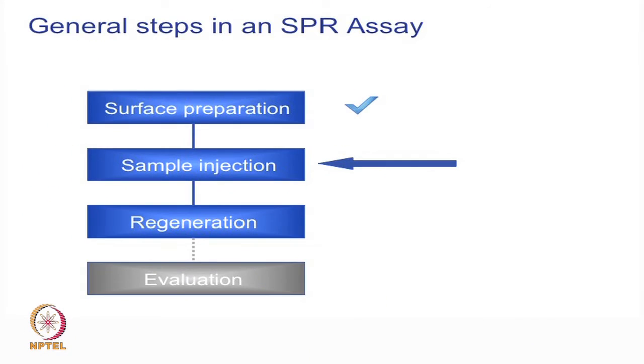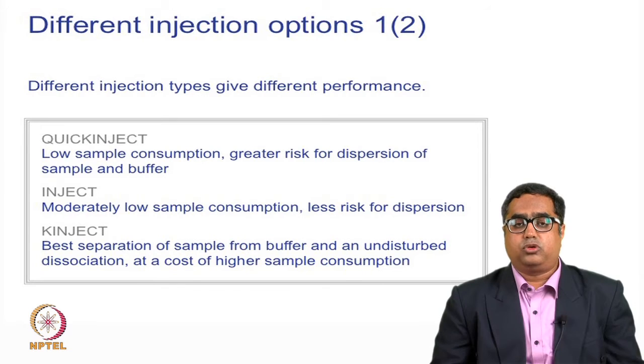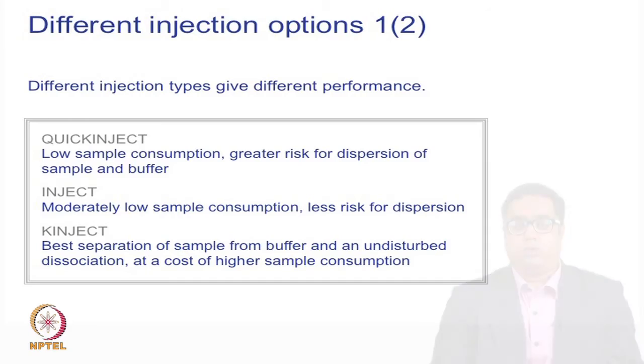The next important step is sample injection. The way molecules are injected depends on the molecular interaction process. For screening, there is a slow injection; for kinetics, a certain flow rate is used. The different injection modes are called quick inject, kinject, and inject. The mode changes based on whether you are doing screening, kinetics, or thermodynamics, and the injection process and contact time change accordingly.